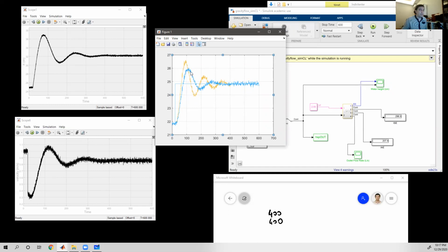I'll come to that overshoot ratio in a minute. Then let's see, the decay ratio is, as you can see, much smaller, or about 1/4. So this is pretty good. So let's see what the value here is. It's about 25.08 compared to the set point. This is like 0.3 units. And this is like 1.2, so 0.3 over 1.2, yes, this is almost exactly 1/4 of decay ratio, so that's pretty good.